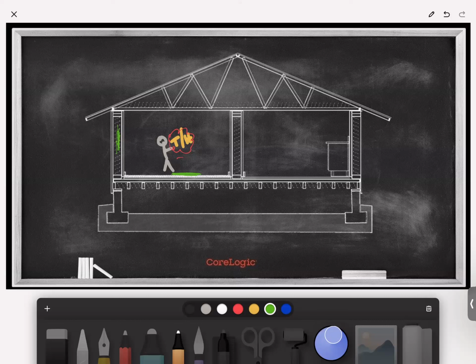So for that reason, one of the most basic things in psychrometrics that we need to understand is that one reading inside of your affected area or your affected drying chamber isn't really fitting the bill. Now, this is an important reading, because I'm going to use that as a point of comparison. I'm going to compare that to these other locations where water exists. And if that reading looks wonderful, but the reading down at location 1 on my floor does not, then I'm missing a really important element in the drying process.